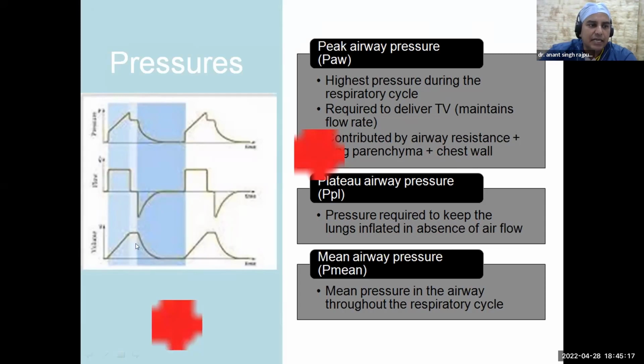We have to understand that volume is being delivered. This is a volume against time curve. So volume is being delivered, then the volume is being held at the same position, and then the expiration starts, and the volume starts reducing inside the lung. So this is a volume against time curve, this is a flow against time curve, and this is a pressure against time curve, right? So what is peak airway pressure? It is the highest pressure during the respiratory cycle. What is plateau pressure? During the pause, whatever pressure you achieve is plateau pressure. What is mean pressure? Overall, including inspiration as well as expiration, what is the mean pressure in the airway throughout the respiratory cycle? That will be called mean airway pressure.